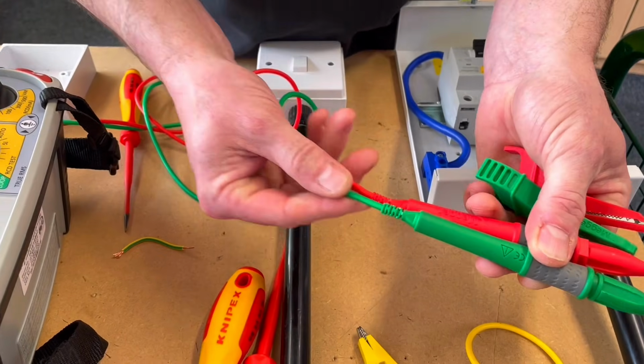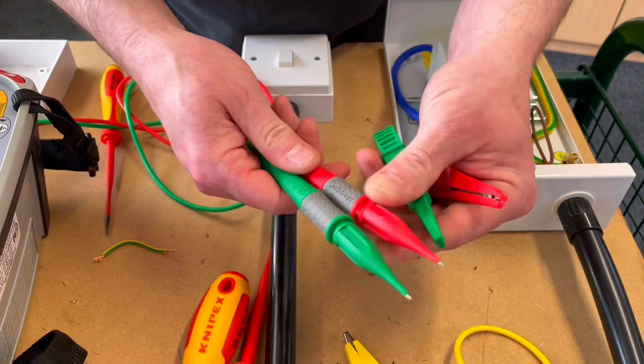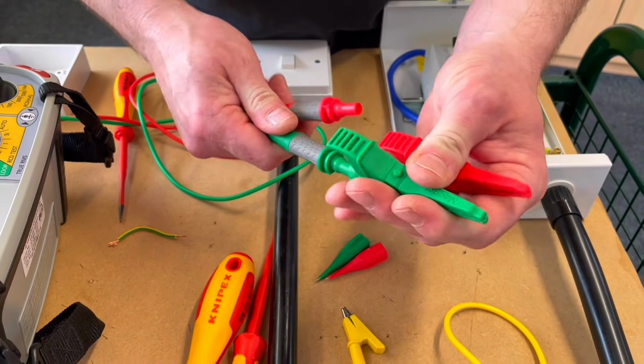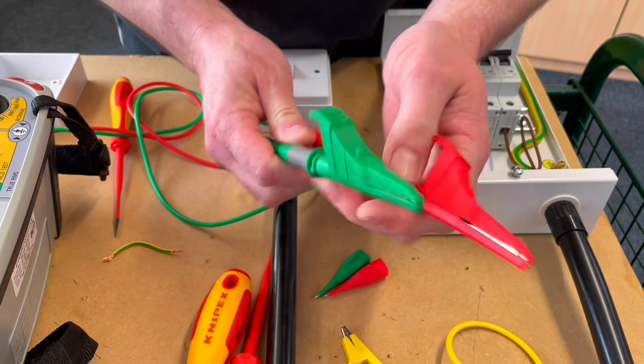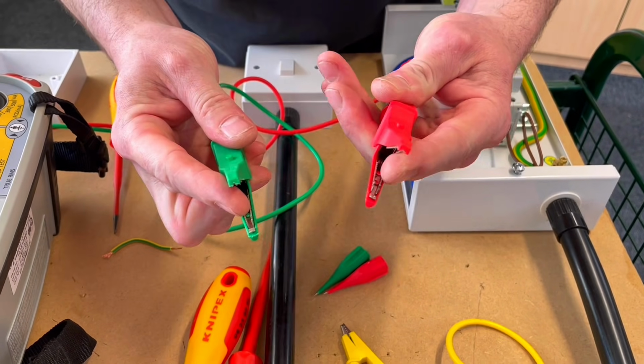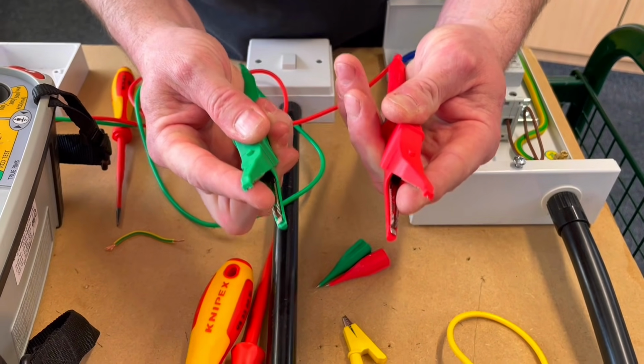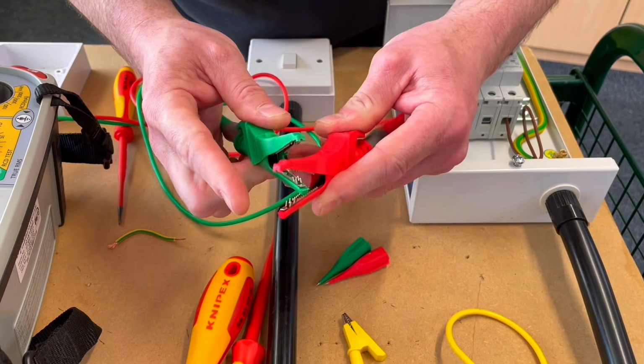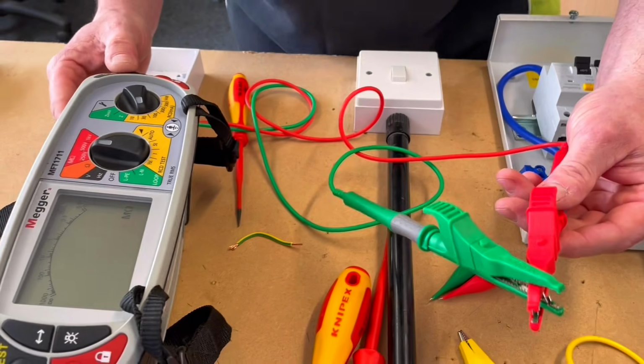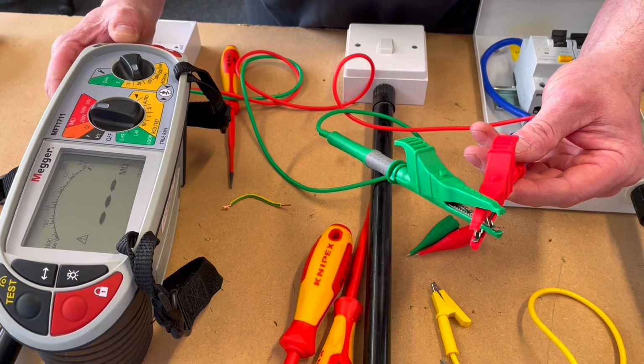Just to prove these leads haven't been damaged during the first test, I'm going to short them together on this scale. So I'm going to remove the tips and put the crocodile clips on. I don't want to get my hands on the end of here. If I was going to touch both of these ends, I would obviously pass 500 volts through myself. Remember, that's 500 volts DC. So I'm going to link the two together. I'm going to press and hold my test button now. It doesn't automatically do this test.